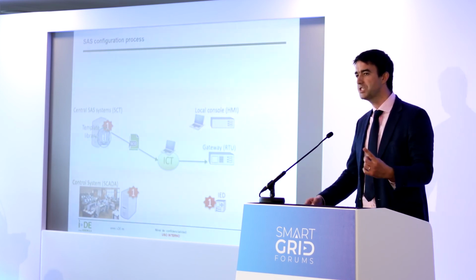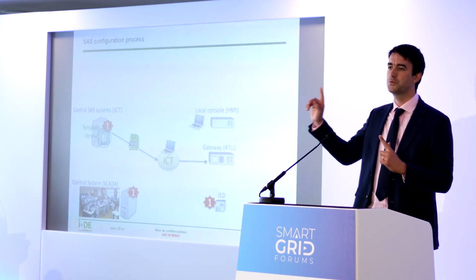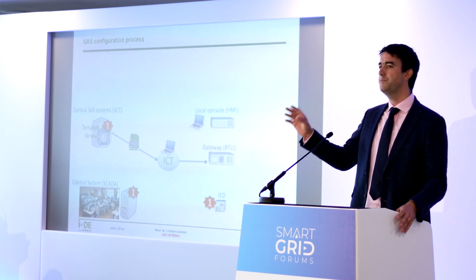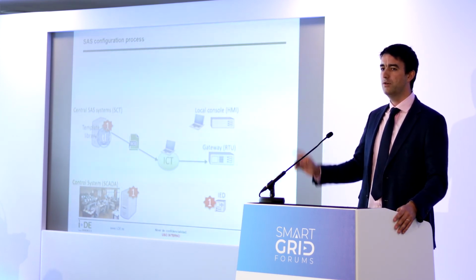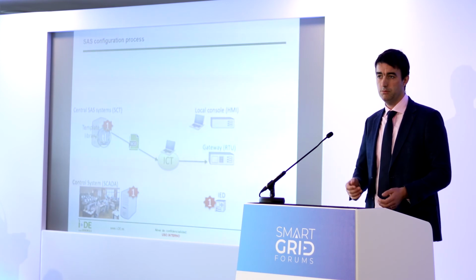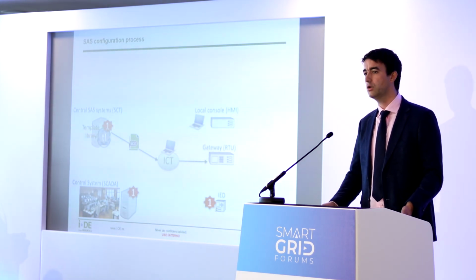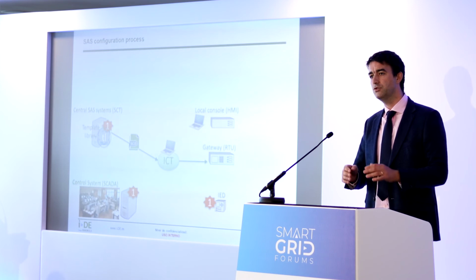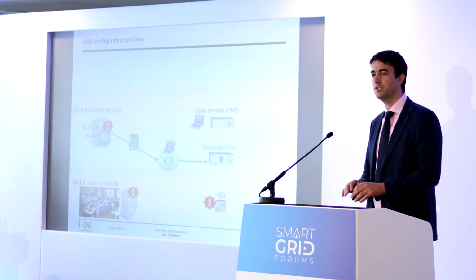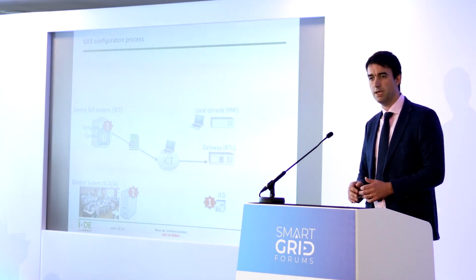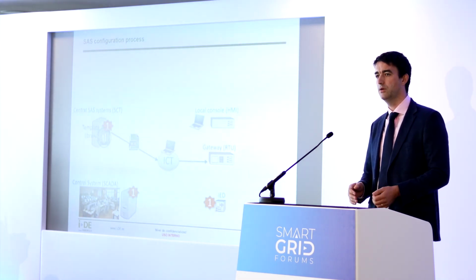The IP in the SCD file is not used to configure the IP address of the IED. Rather, the IP of the IED must be configured locally first, either using the IED's HMI or the IED configuration tool with a local connection. The configuration file, which includes the IP address, will then be rejected by the IED tool or the IED itself if it is not consistent.